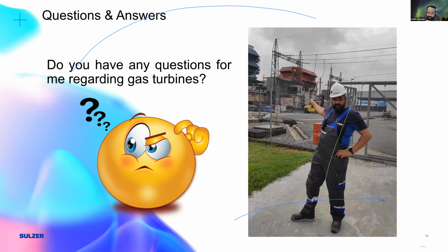Okay, thank you too. To answer maybe the second question, this is specific to the DCS. So if you have T3000 version 9 ongoing, you have to do the calibration within the DCS - there's a specific block in the logic. With regards to HART, I'm not familiar. I think you're talking about industrial turbines - they might have what you call the MOOG controller, or like with GE, they have the LVDTs. So you might need external equipment to do that, but typically with these ones, you do it with the DCS system.